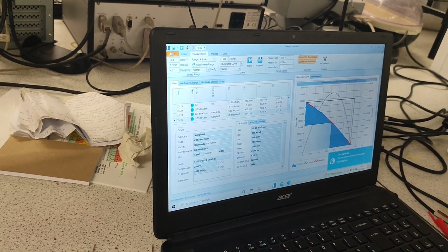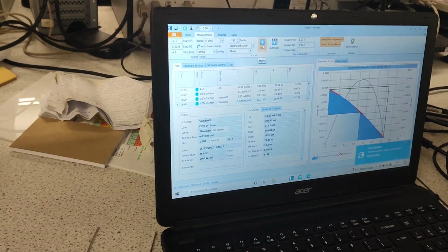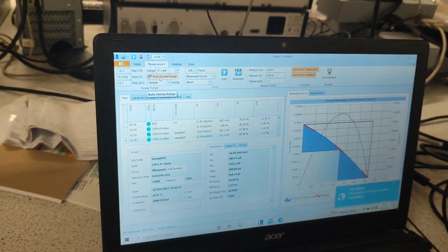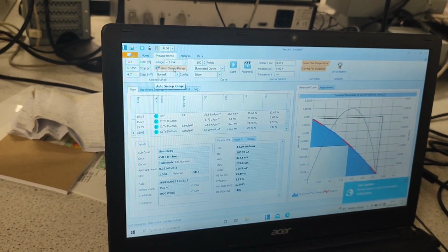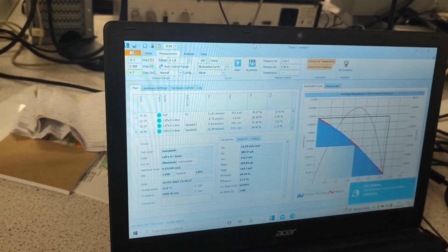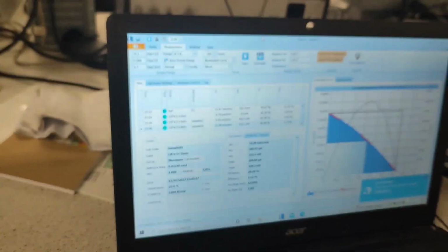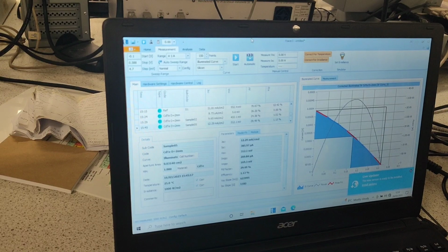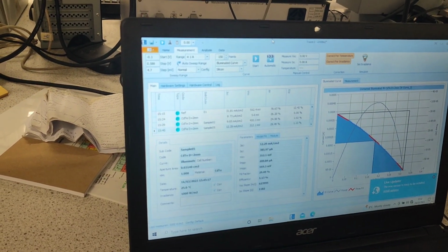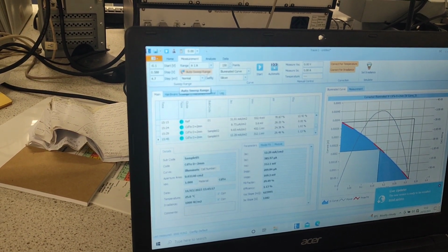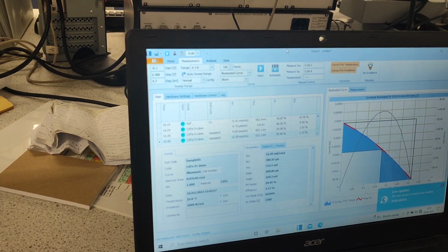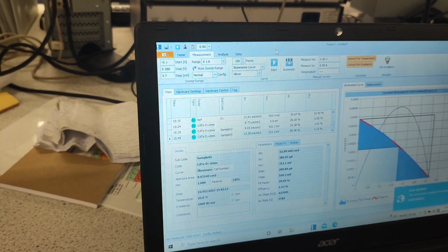Now before we click start, the last thing we need to do is click on auto sweep range over here, in order to set a voltage range that is applied automatically by the instrument itself. Once I click it, that necessary setup is done automatically by the system. Then we go to start.